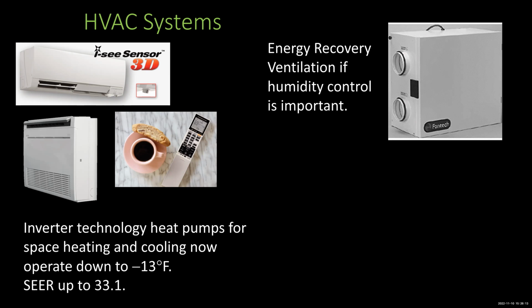Now, if we need humidity control and you have an energy recovery ventilation system, if it brings the incoming air down below the dew point, you're going to need a condensate drain for this thing, because it actually dries the incoming air a little bit as well.